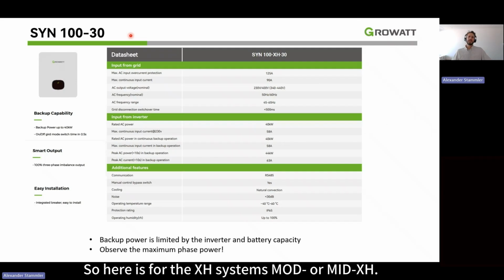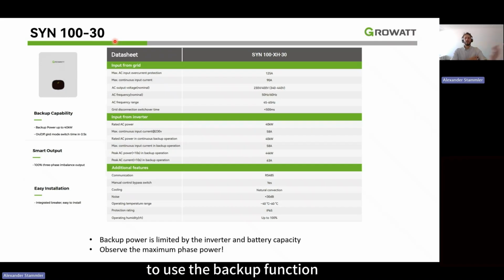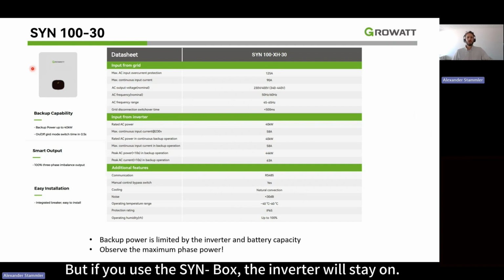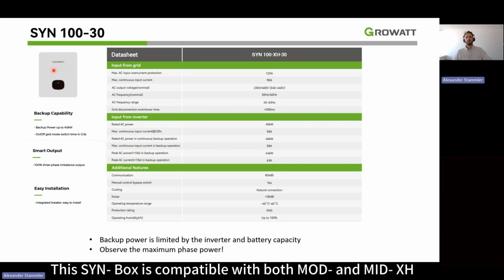So here is for the XH systems, MOD or MID XH. We need an extra backup box to be able to use the backup function. In case the grid goes off, the inverter would usually turn off, which is a demand. But if you use the SYN box, the inverter will stay on. This SYN box is compatible with both MOD and MID XH, not with the HU system, which I will introduce later.